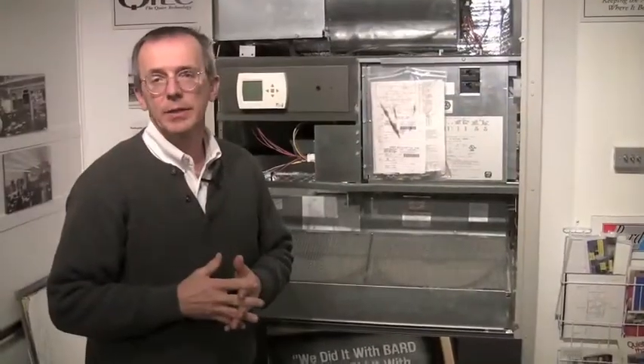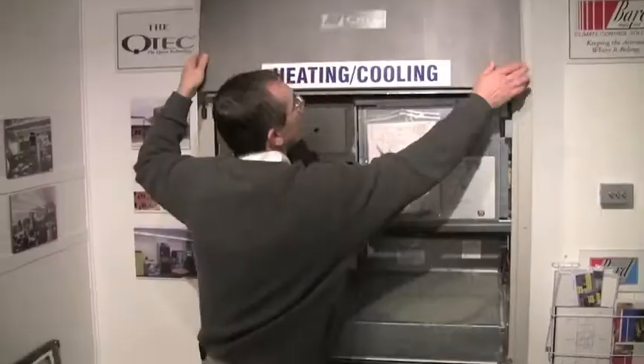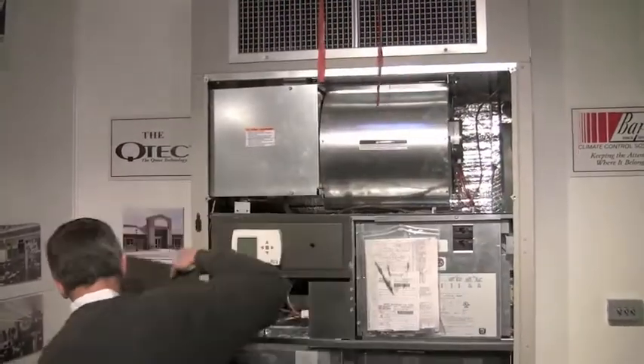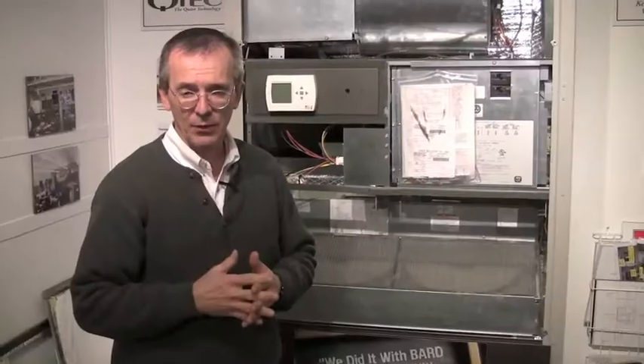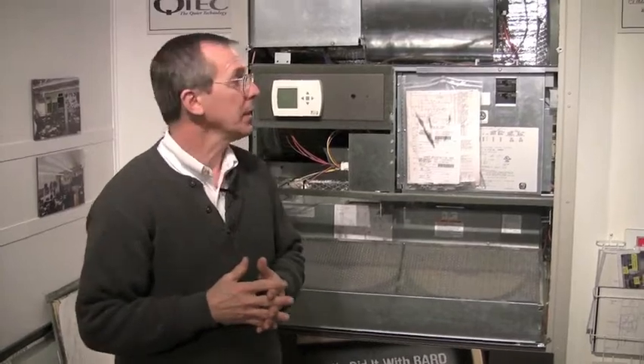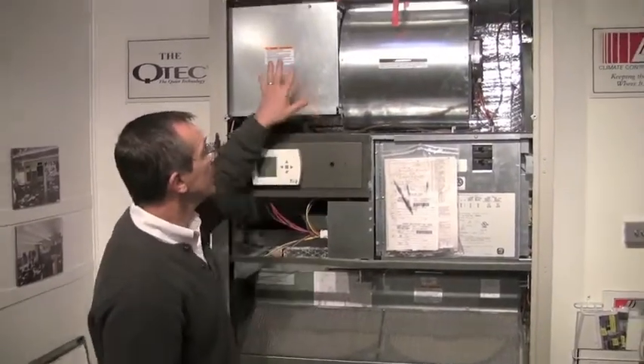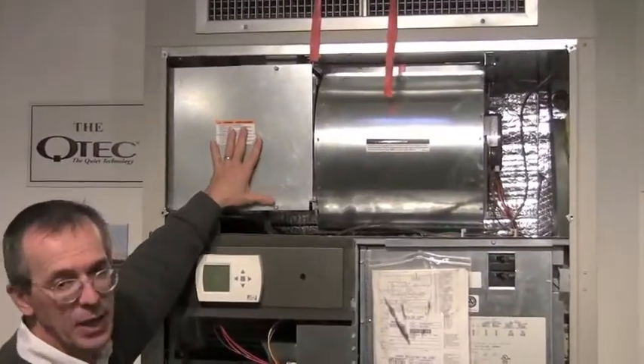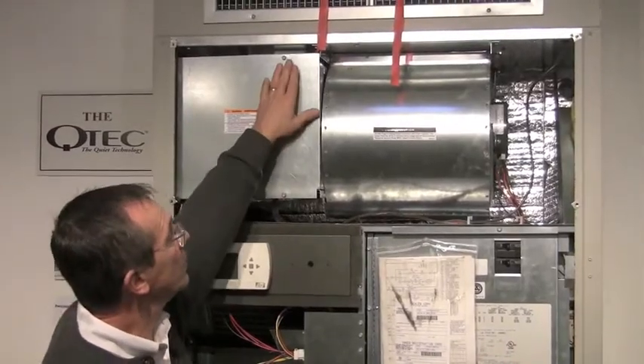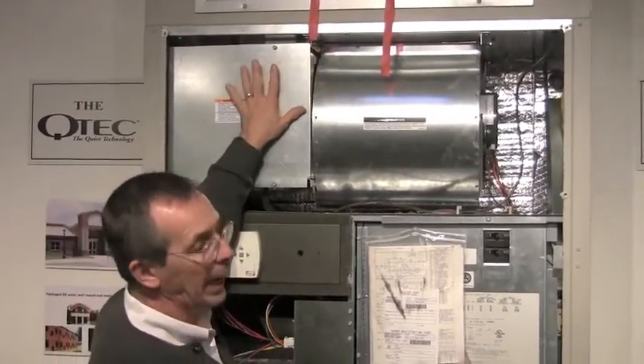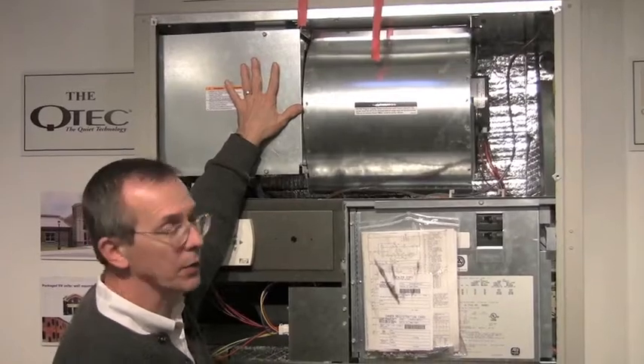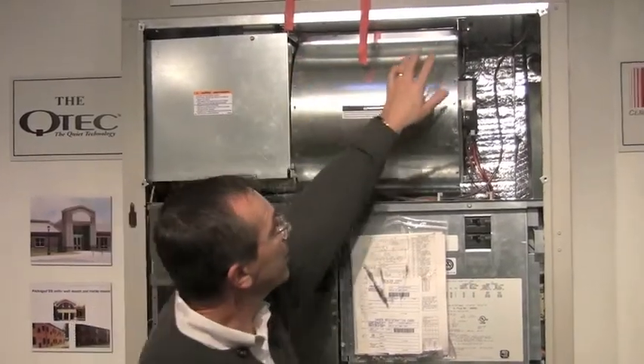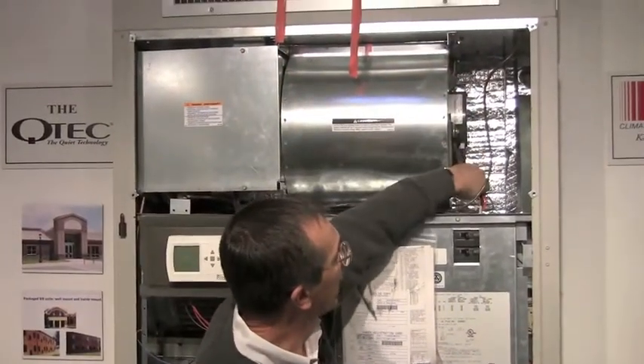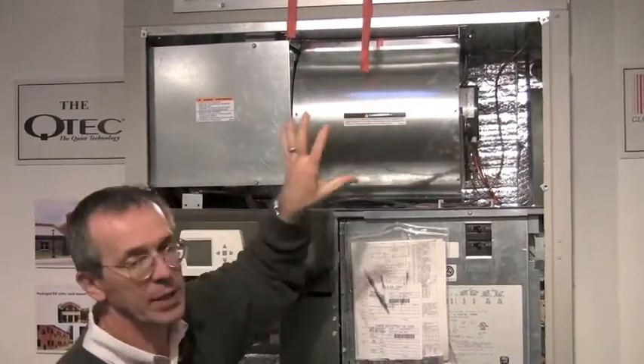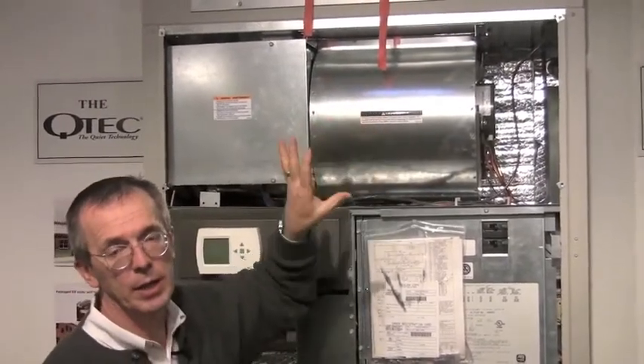The Q-Tec has a GE ECM motor. It starts out soft, it ramps up to speed, and in dehumidification it goes to 3/4 speed. This is the blower section. This is the electric heat section. Remove this screw, and you expose the electric heat for service. Remove this screw here, and this Molex plug, and the whole condenser, or the whole blower section, is out.